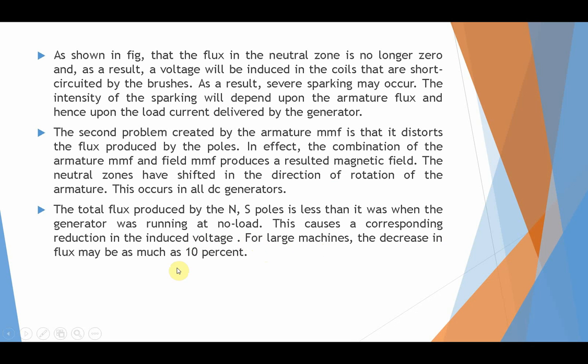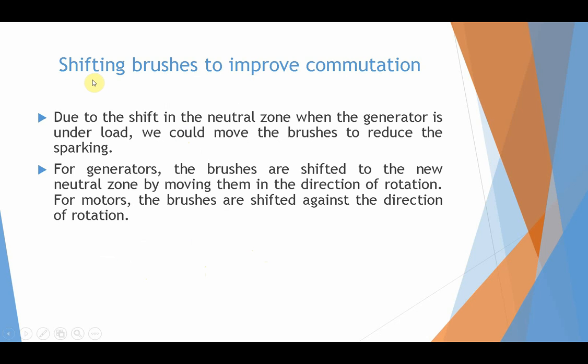For large machines, the decrease in flux may be as much as 10%. To improve commutation, we can shift the brushes. Due to the shift in the neutral zone when the generator is under load due to armature reaction, we move the brushes to reduce sparking. For a generator, the brushes are shifted to the neutral zone by moving them in the direction of rotation.